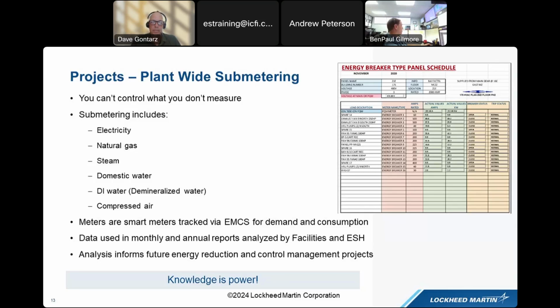Everything of any importance is trended. We can tell how much capacity we have left on a panel, a feeder, or a unit sub, and determine whether we're going to have to pull a new feeder, which is terribly expensive, or if we can expand the existing one by adding additional breakers. That can save millions on a project. That's the type of savings that can be hidden sometimes, when somebody asks if it's really worth expanding the capabilities of our building management system.